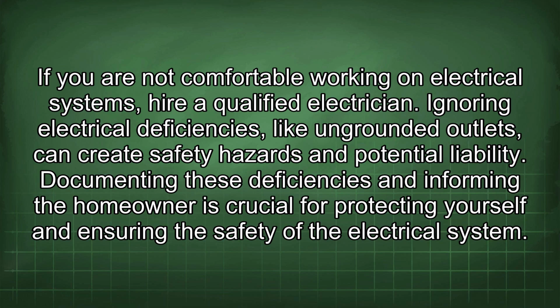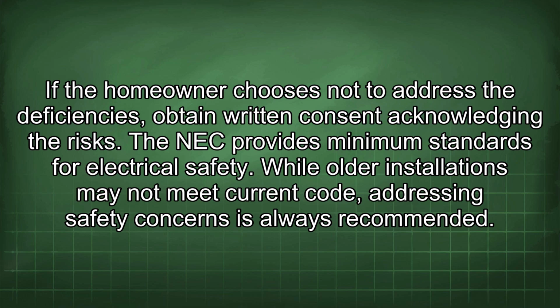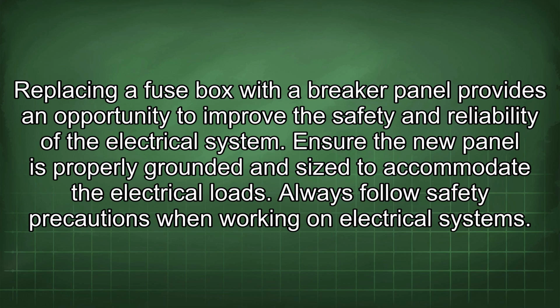Ignoring electrical deficiencies, like ungrounded outlets, can create safety hazards and potential liability. Documenting these deficiencies and informing the homeowner is crucial for protecting yourself and ensuring the safety of the electrical system. If the homeowner chooses not to address the deficiencies, obtain written consent acknowledging the risks. The NEC provides minimum standards for electrical safety. While older installations may not meet current code, addressing safety concerns is always recommended. Replacing a fuse box with a breaker panel provides an opportunity to improve the safety and reliability of the electrical system. Ensure the new panel is properly grounded and sized to accommodate the electrical loads. Always follow safety precautions when working on electrical systems.